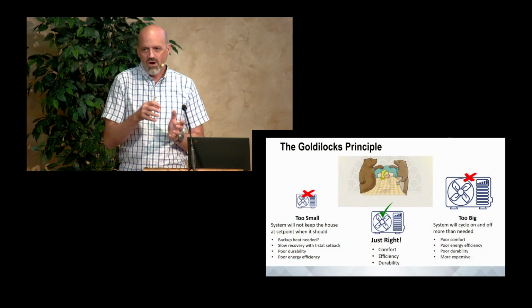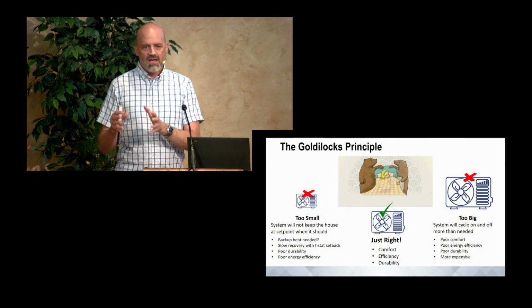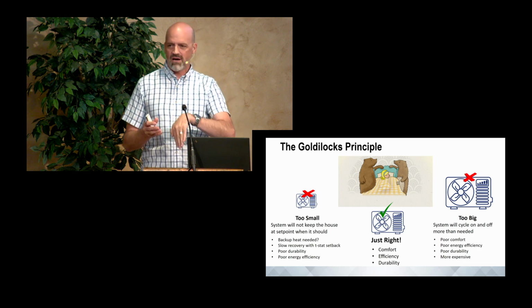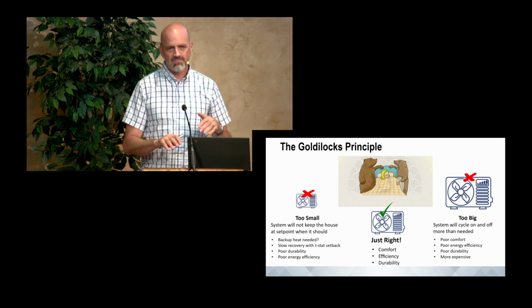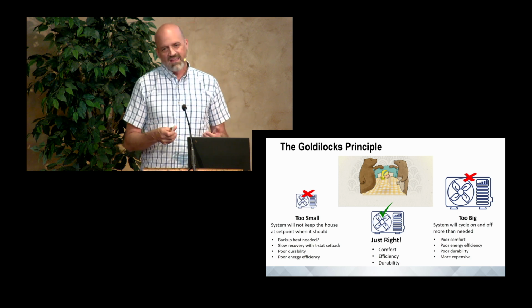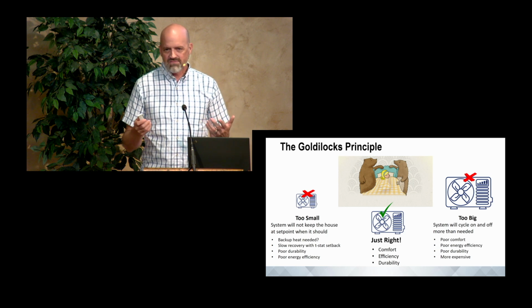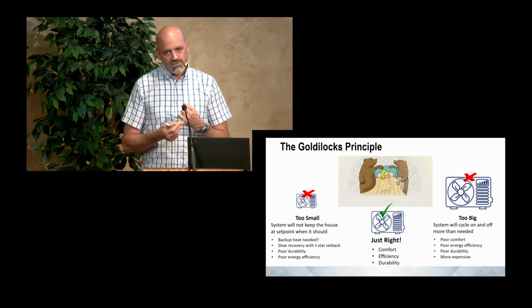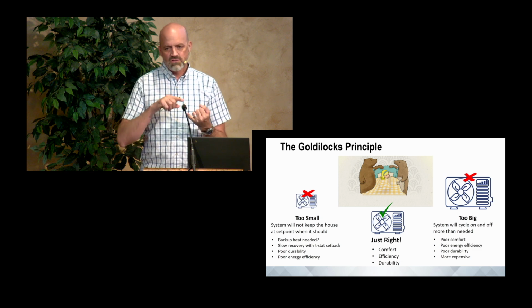Why not just take a piece of equipment that we know is going to cover the heat load, put it in, and trust that it's going to modulate and step down to take care of what we need? It might not be quite as efficient all the time, but we know we're covered. Well, you also start to give up a little bit of comfort, because you run the risk of short cycling happening.